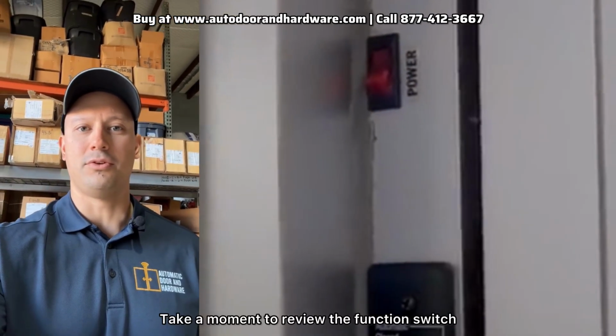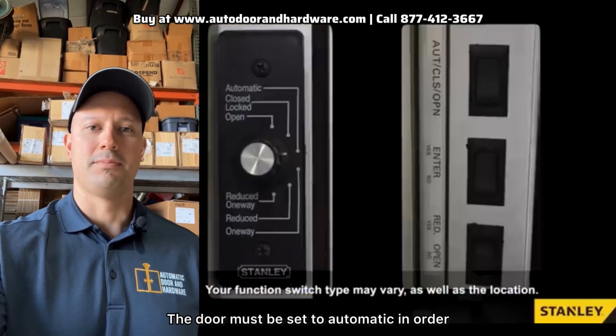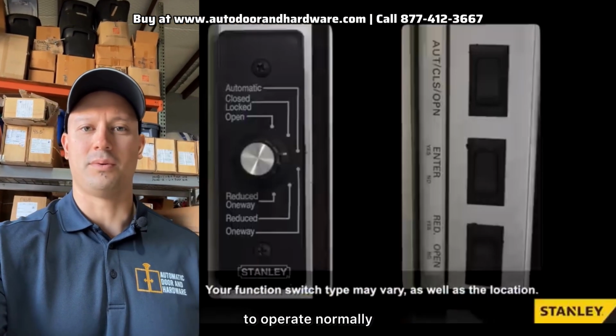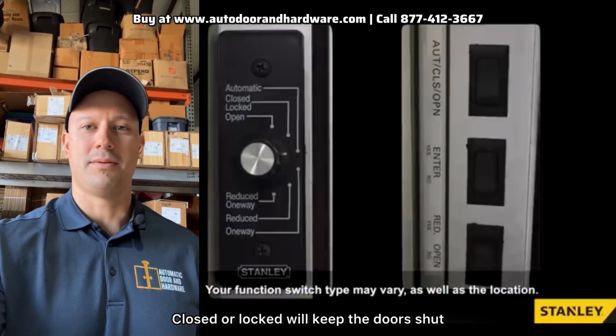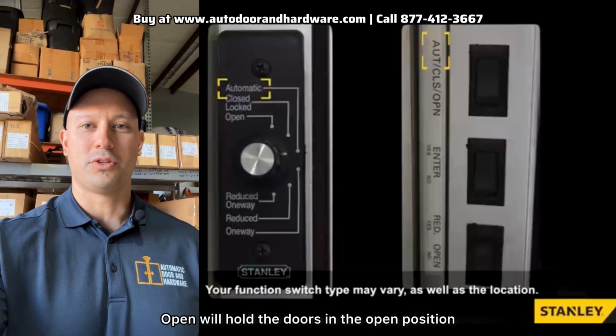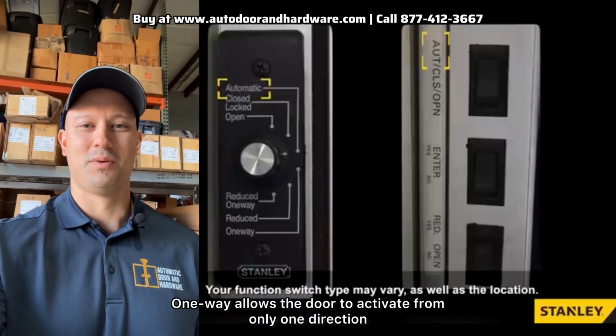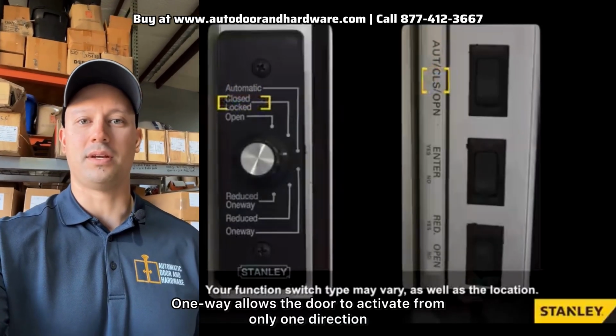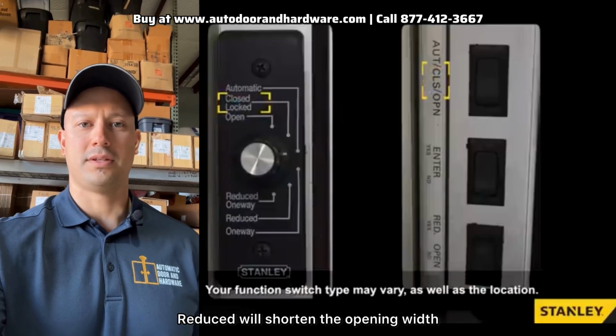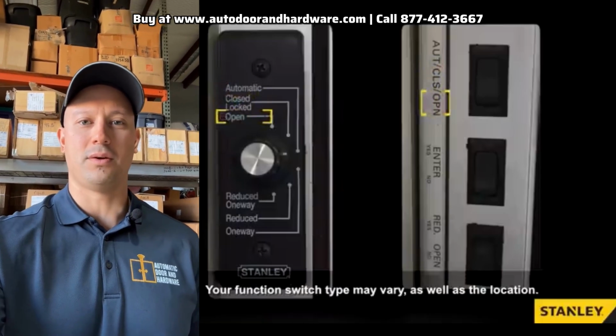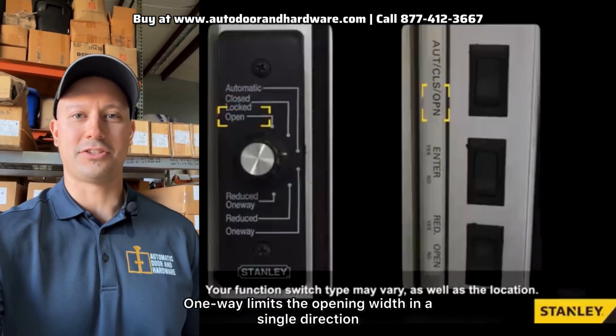Take a moment to review the function switch. The door must be set to automatic in order to operate normally. Closed or locked will keep the doors shut. Open will hold the doors in the open position. One way allows the door to activate from only one direction. Reduced will shorten the opening width. Reduced one way limits the opening width in a single direction.